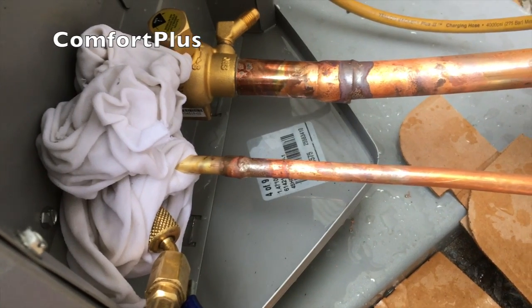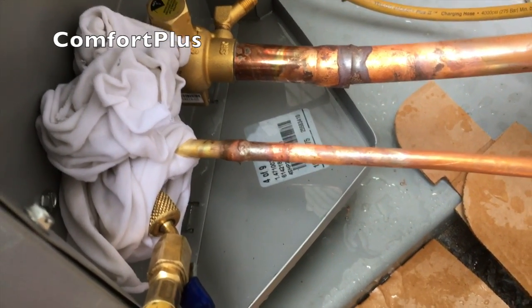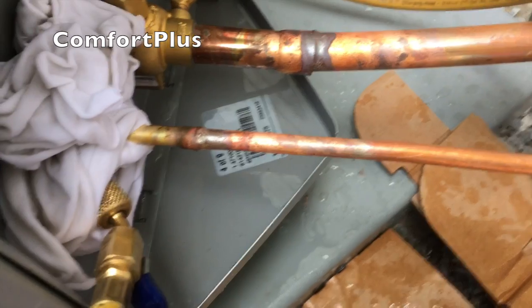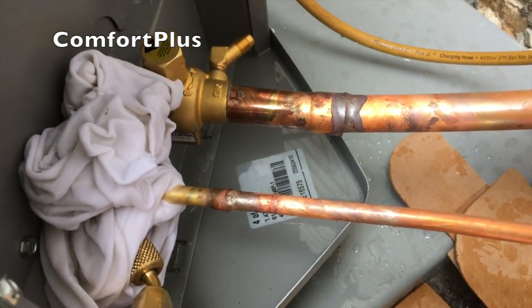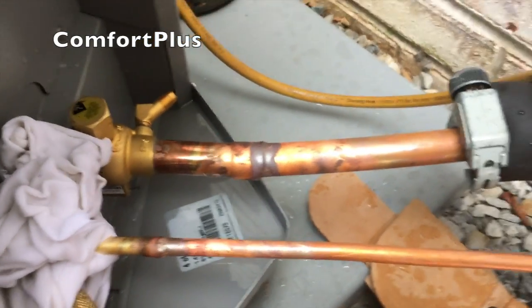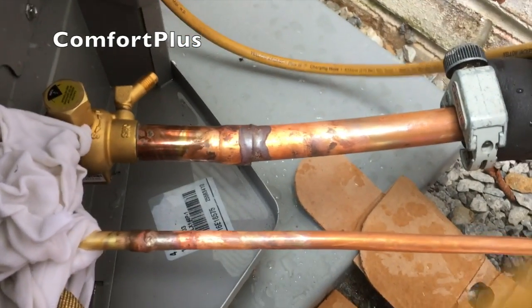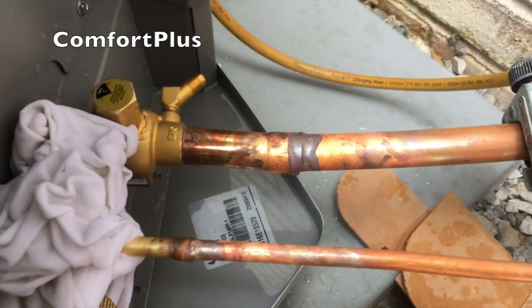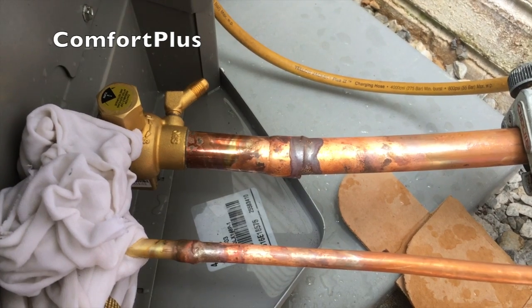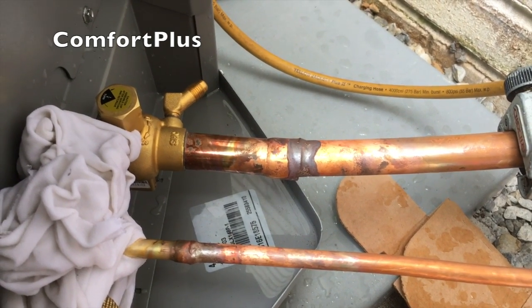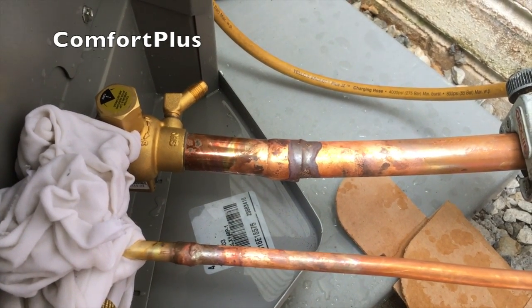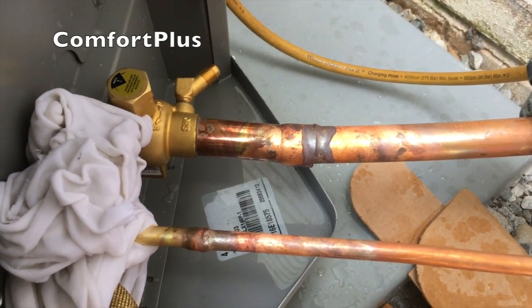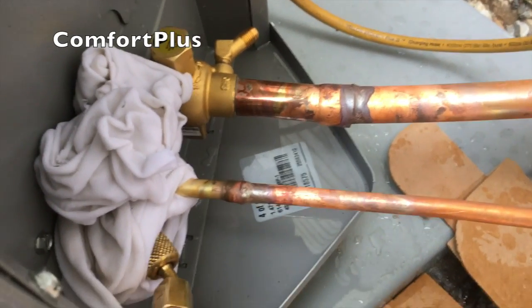Okay, the outdoor unit's welded up. I got the inside lines uncapped. I've got to go in and make a few bends on it and connect it to the air handler. I've cut off about 6 inches out here, maybe 7, and I may cut off just a couple inches inside, but that'll be a 50-foot line set minus those 2 little pieces I cut off.